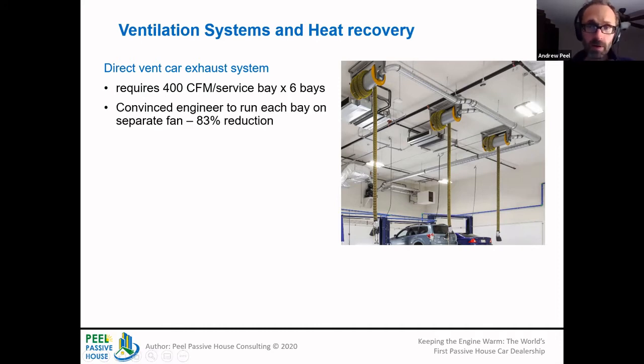Now, the standard approach is to put all the tubes connected to one fan and just eject it outside. We were able to convince the engineer to have a separate fan per bay. And so you can see an 83% reduction in our total flow. One thing I forgot to explain is that with one fan, when you have one car going and you need one tube sucking, all service bays would exhaust at the same time. So even though you may only need 400 for one bay, you're actually running at 2,400. We were able to reduce that to just 400 at one time.